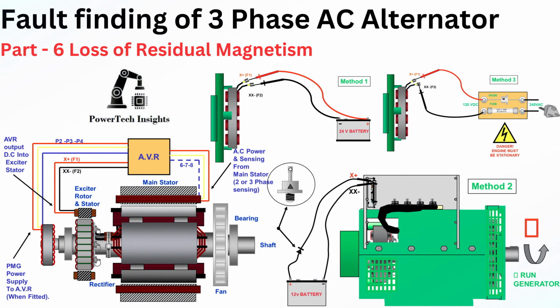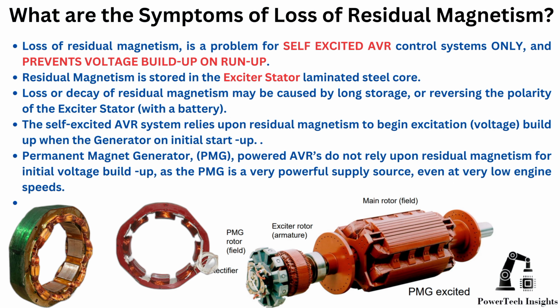Part 6, the loss of residual magnetism. In this part, we will provide a comprehensive guide on fault diagnosis for the loss of residual magnetism and how to restore residual magnetism. Let's get started. Possible symptoms of loss of residual magnetism. Loss of residual magnetism is a problem for self-excited AVR control systems only and prevents voltage buildup on run-up.